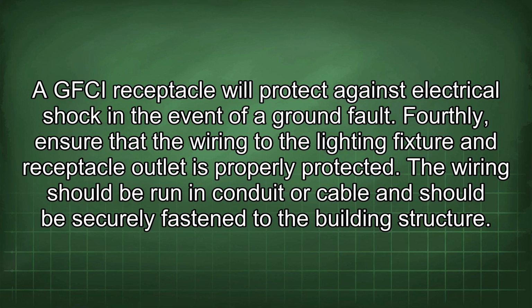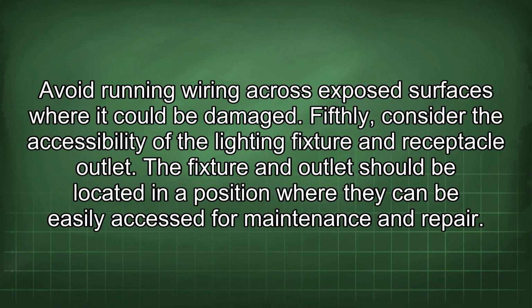Fourthly, ensure that the wiring to the lighting fixture and receptacle outlet is properly protected. The wiring should be run in conduit or cable and should be securely fastened to the building structure. Avoid running wiring across exposed surfaces where it could be damaged.